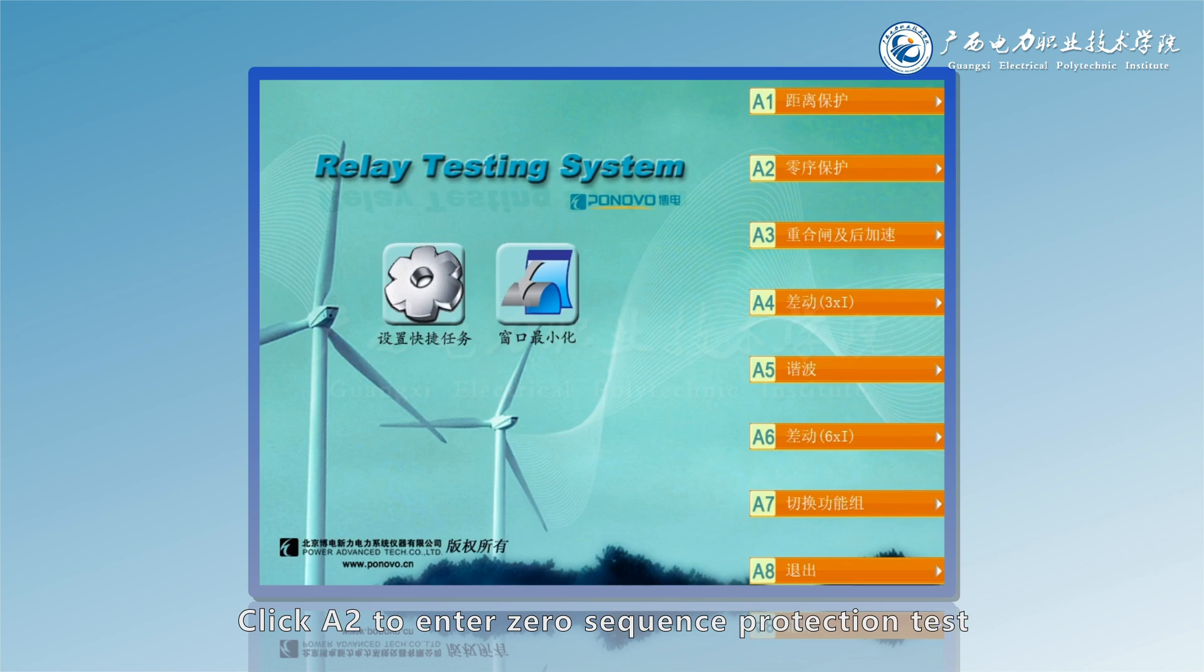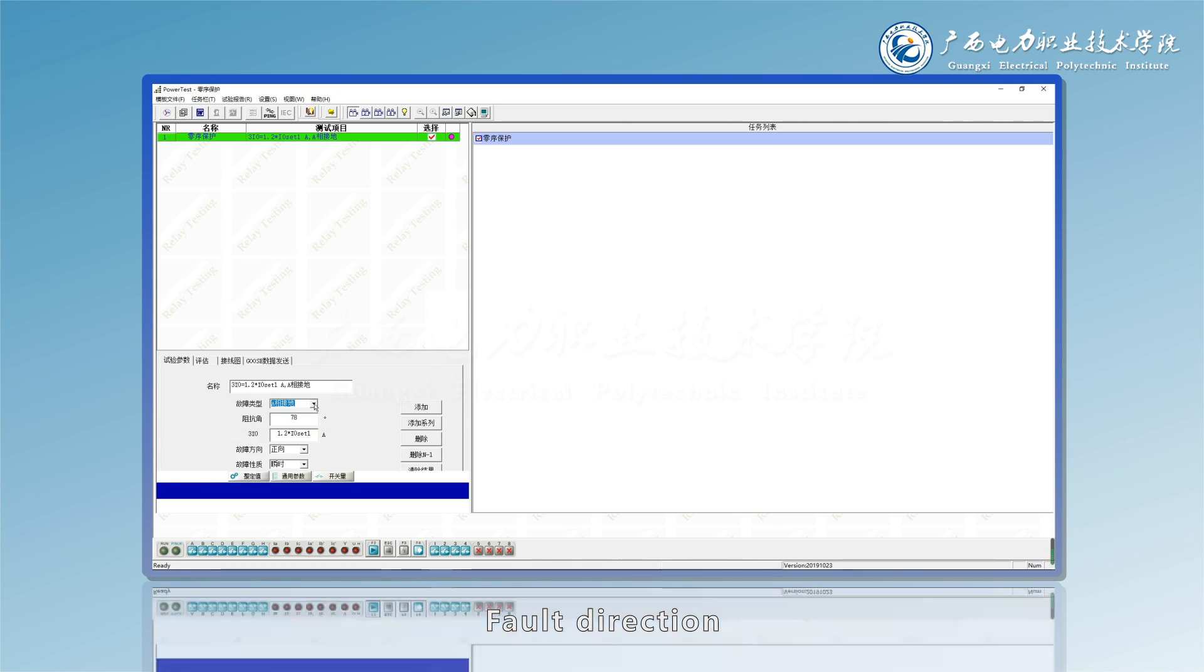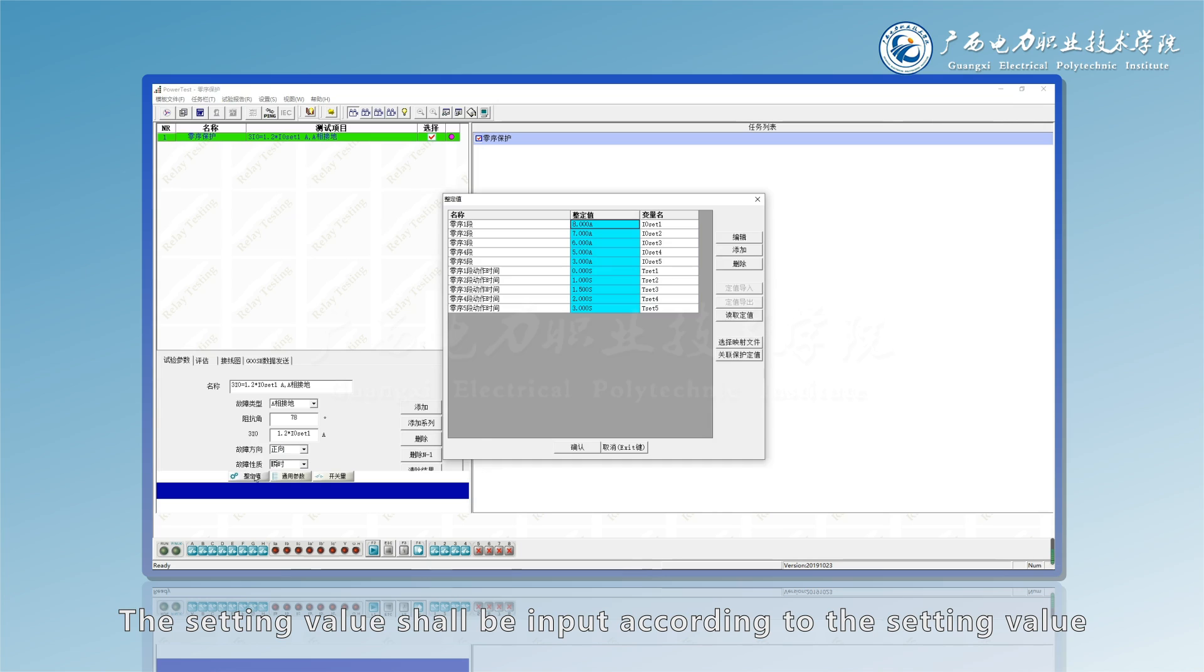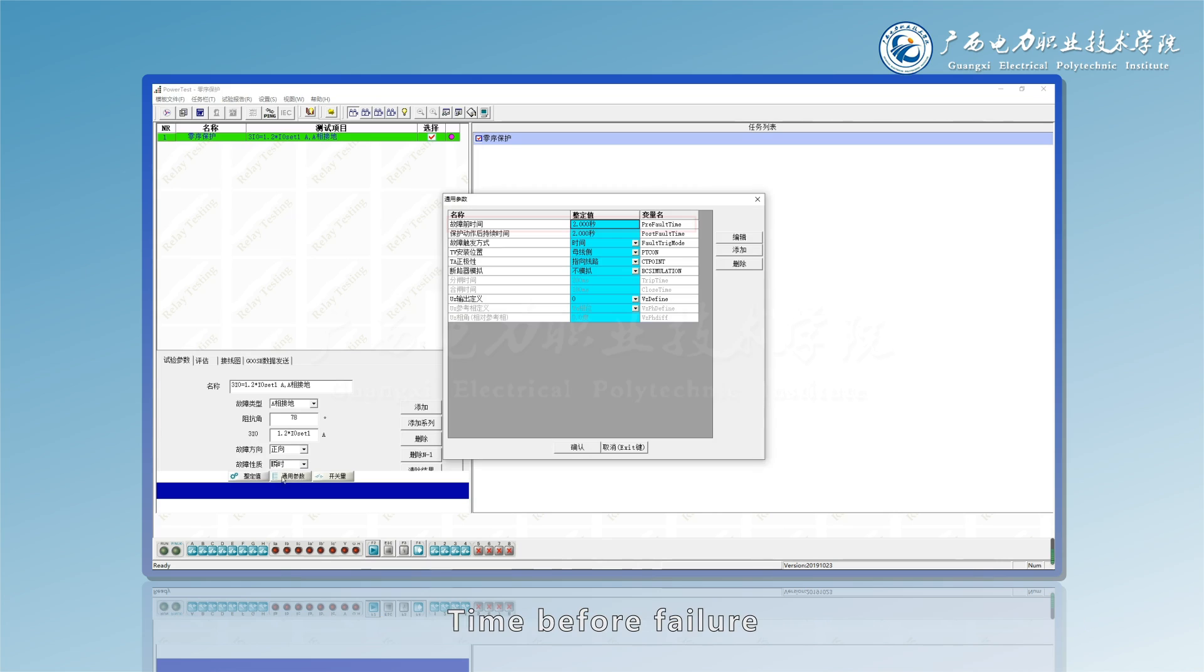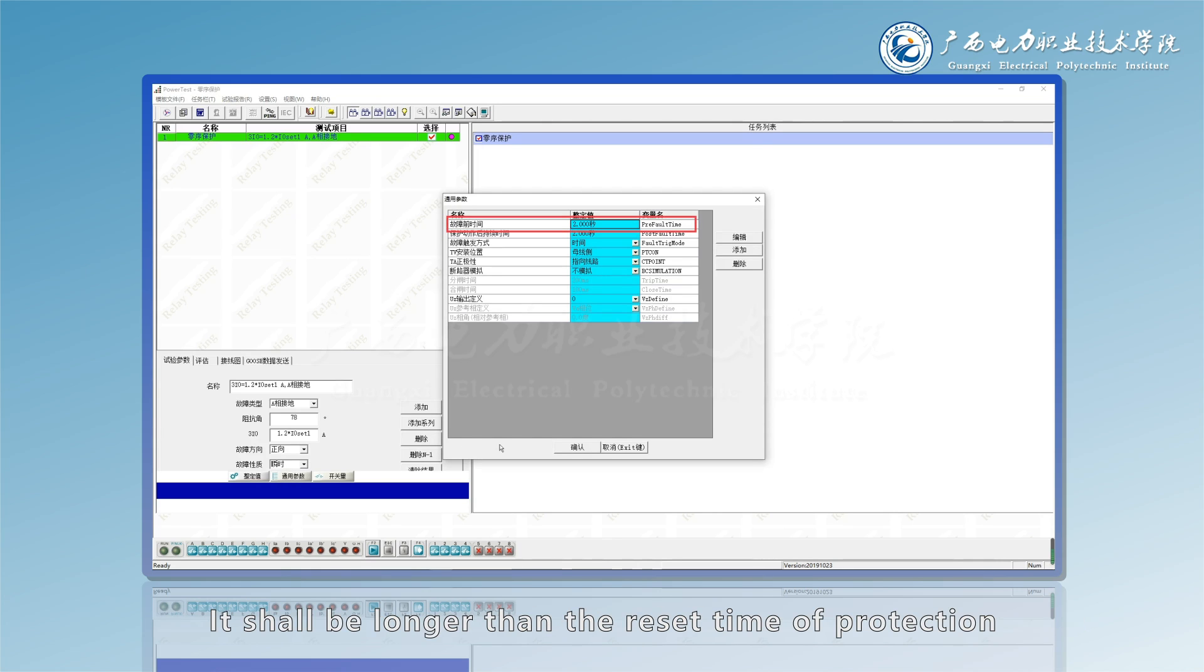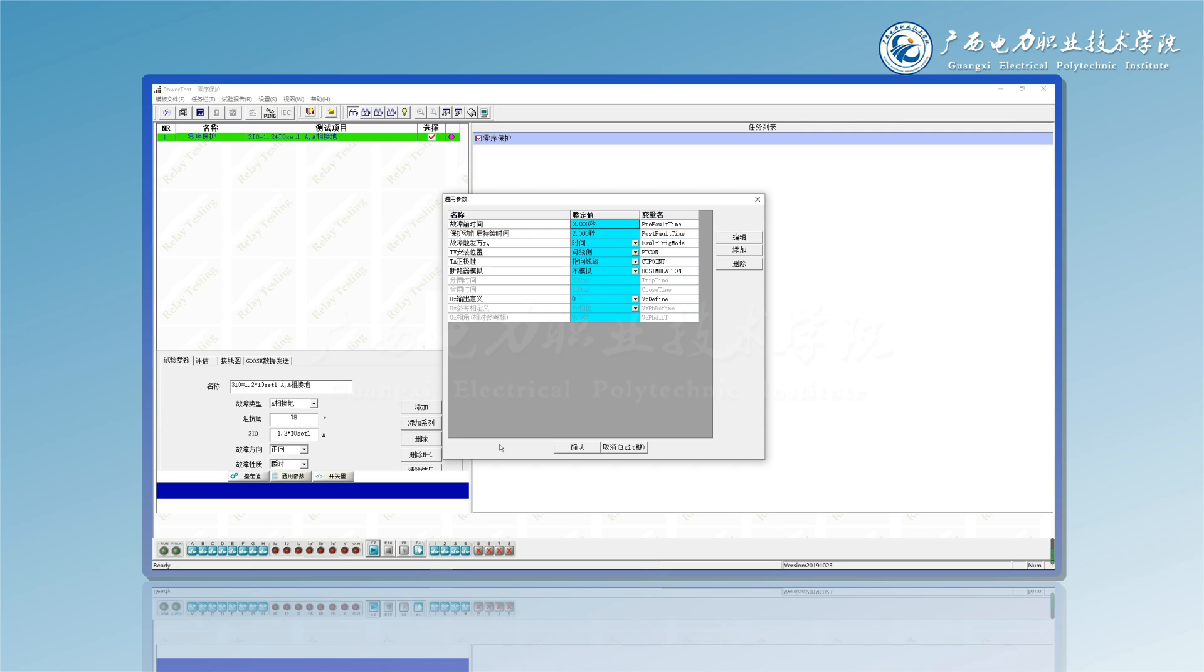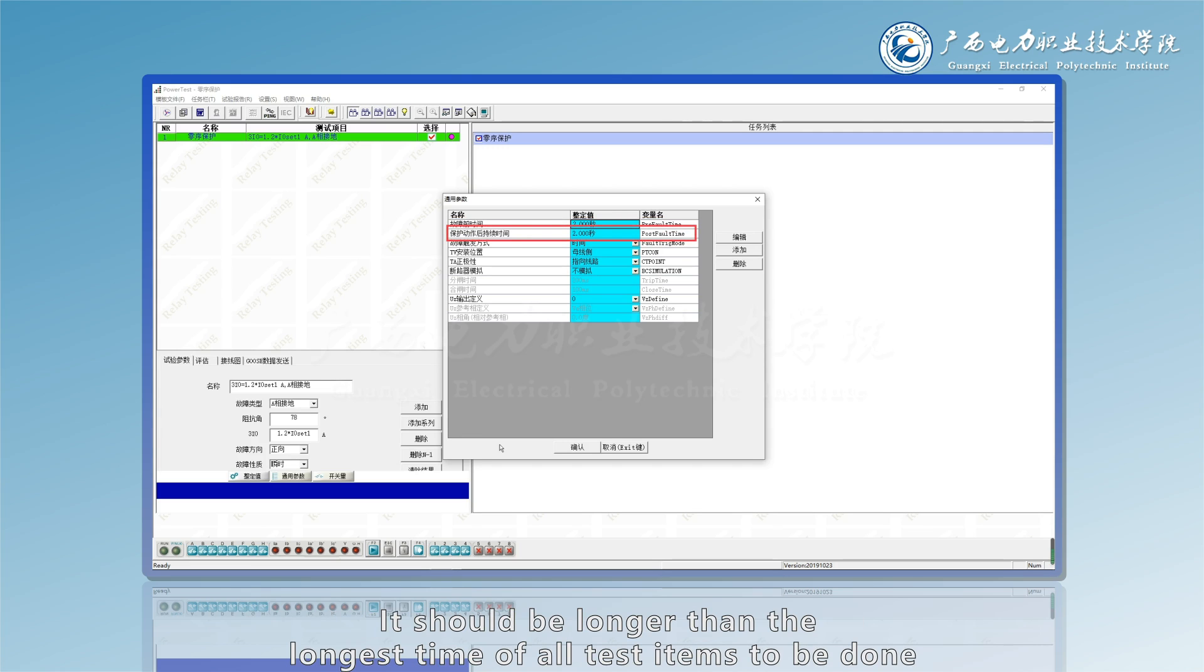Click A2 to enter zero sequence protection test. Select a fault type, fault direction, forward short circuit. The setting value shall be input according to the setting value. General parameters: time before failure, it shall be longer than the reset time of protection, just like the distance protection in front. Duration after protection action: it should be longer than the longest time of all test items to be done.